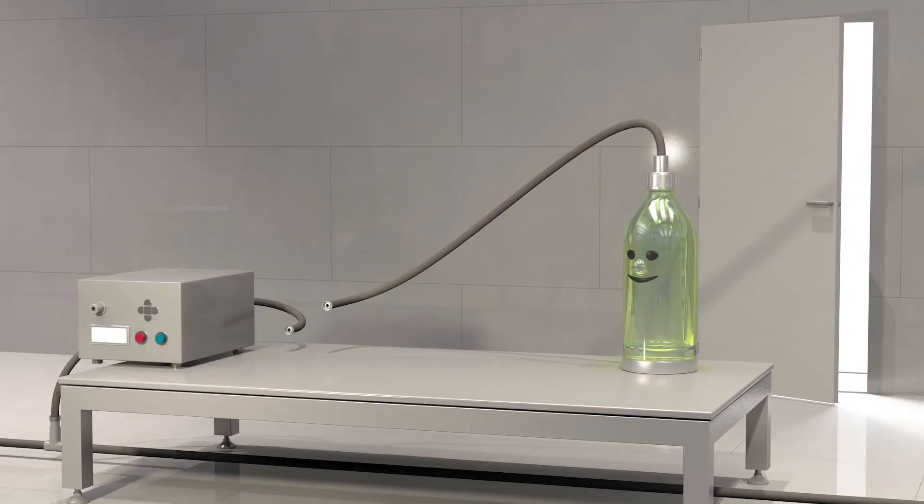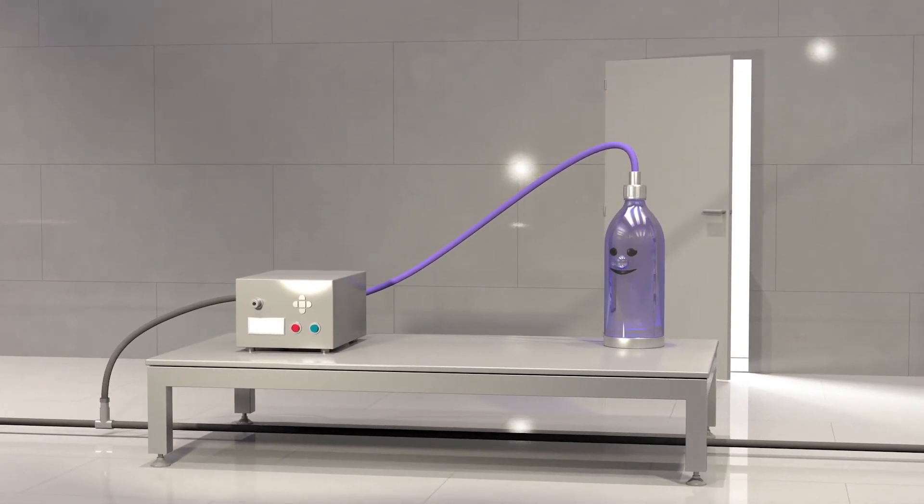A traditional pressure drop instrument, on the other hand, will be affected by these air currents which can create an artificial leak or worse, mask a real leak.